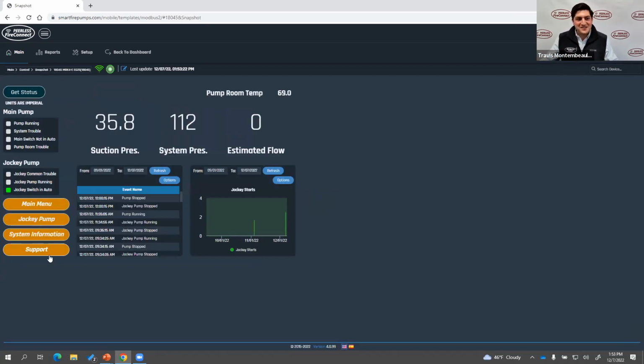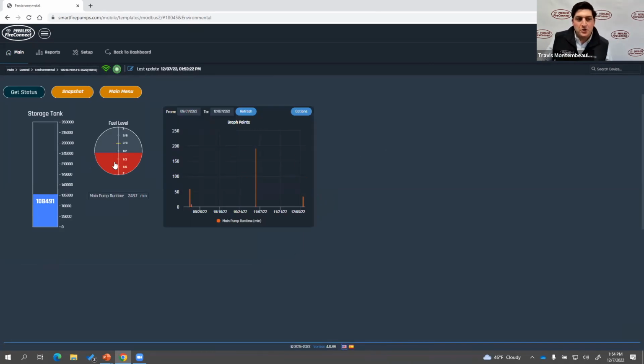And then just the last thing on Sentry here, we did add functionality for monitoring diesel fuel level. And it's alertable. So if you've got a diesel fuel tank, we'll tell you not only if you're high or low, but how much you've actually got in that tank. So when you're looking at, do I need to order fuel? How much fuel do I need to order? I'm only halfway out of the tank. All right, that means I need to get 200 gallons, for example, like that.